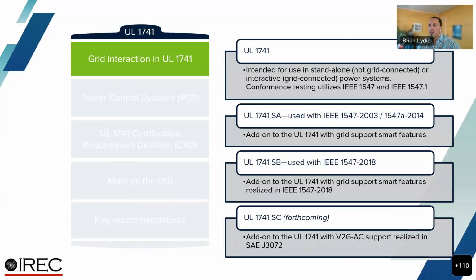Then Supplement SA was created in 2016 to test grid support functionality for so-called smart inverters, and has been used in places like California and Hawaii since 2017. They've required that SA certification since 2017, and that is based on the old version of 1547, either 2003, or there was an update, as Midhat mentioned, in 2014, an amendment allowing for greater ride-through and voltage regulation and whatnot.